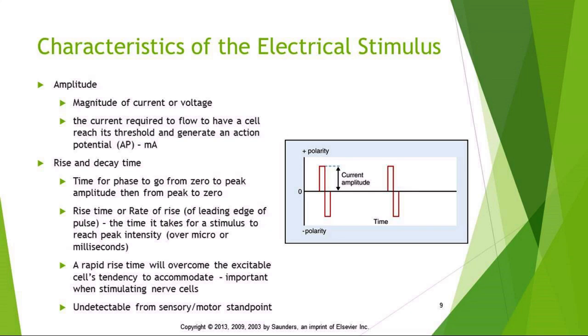So this shouldn't be confused with ramp time. We'll talk about ramp time in a minute. But the rise and decay time is built into the device. The ramp time we can adjust. The rise and decay time is undetectable by human senses. The ramp time is detectable. Okay?